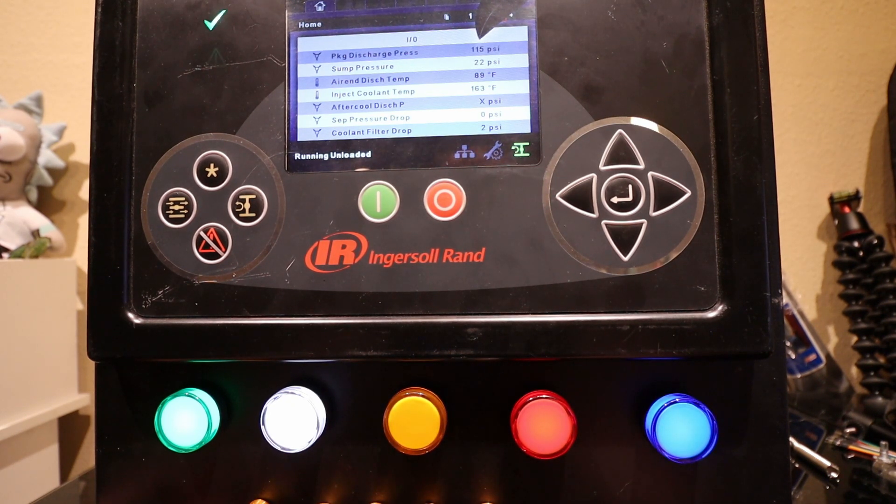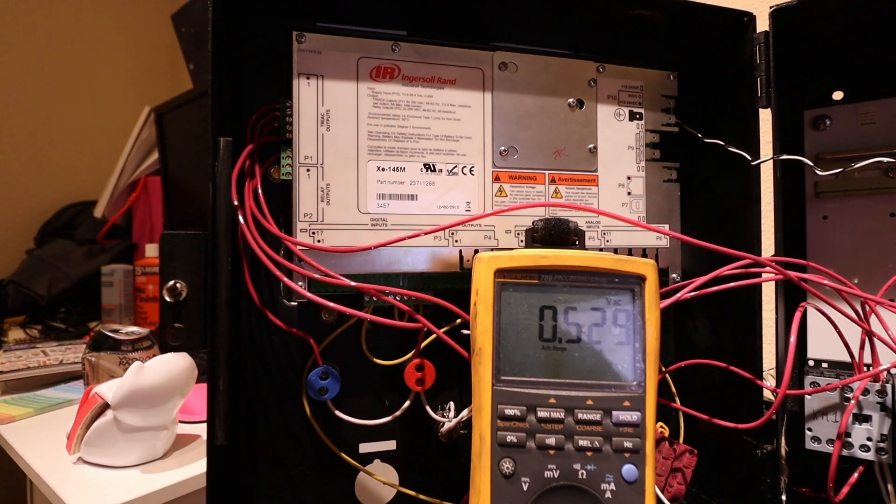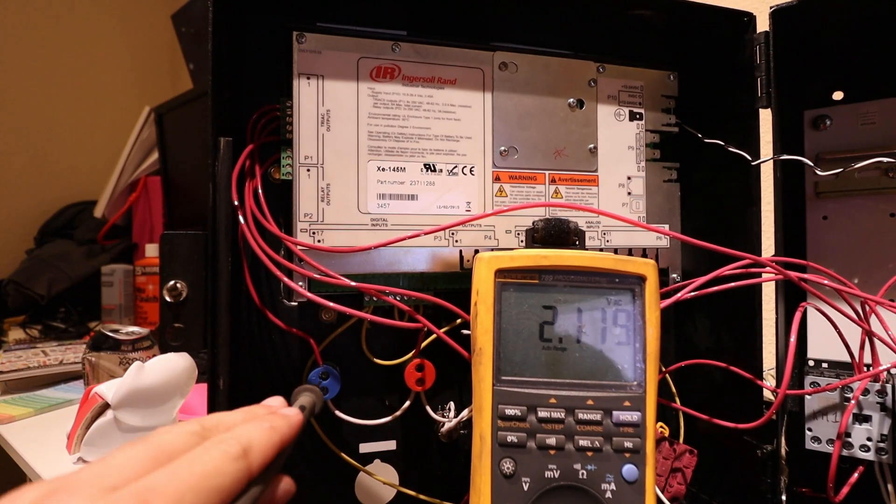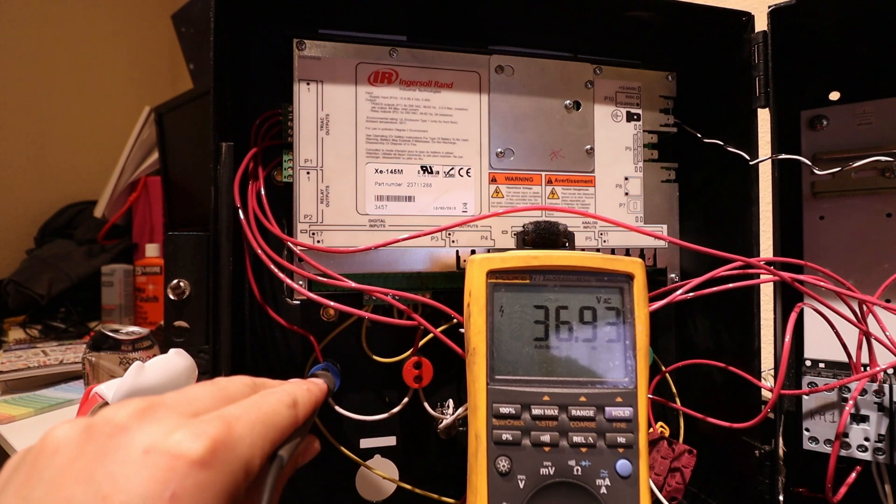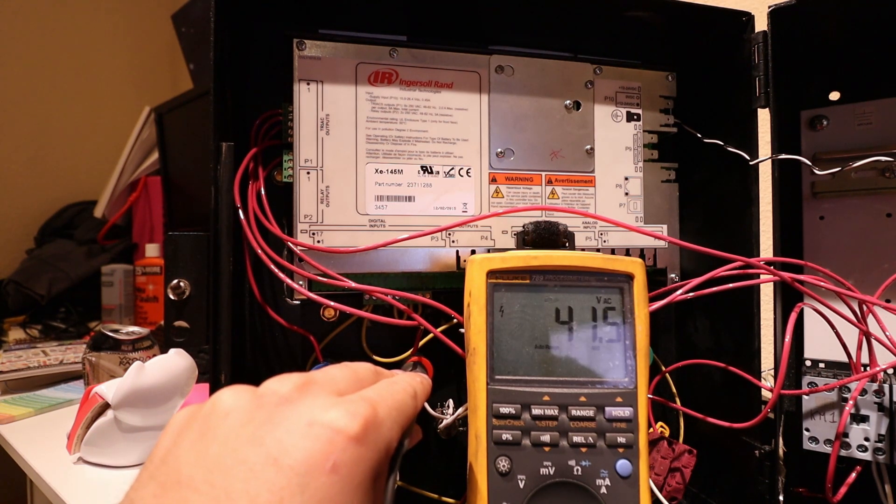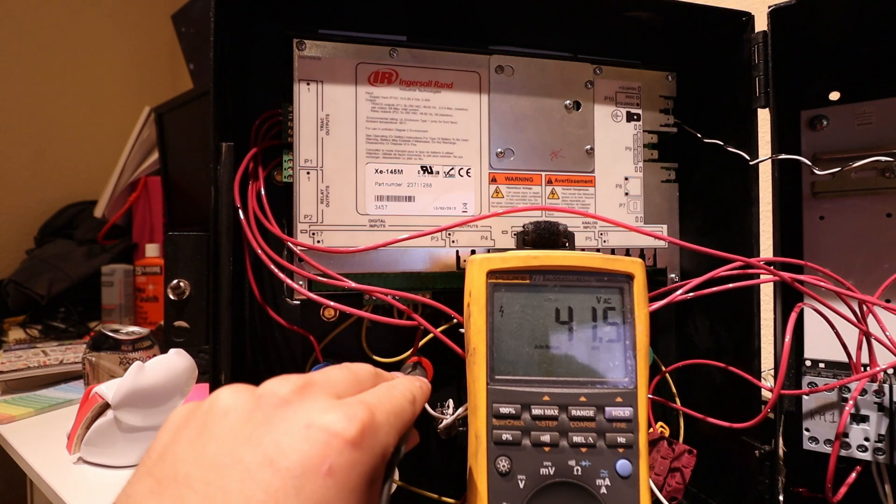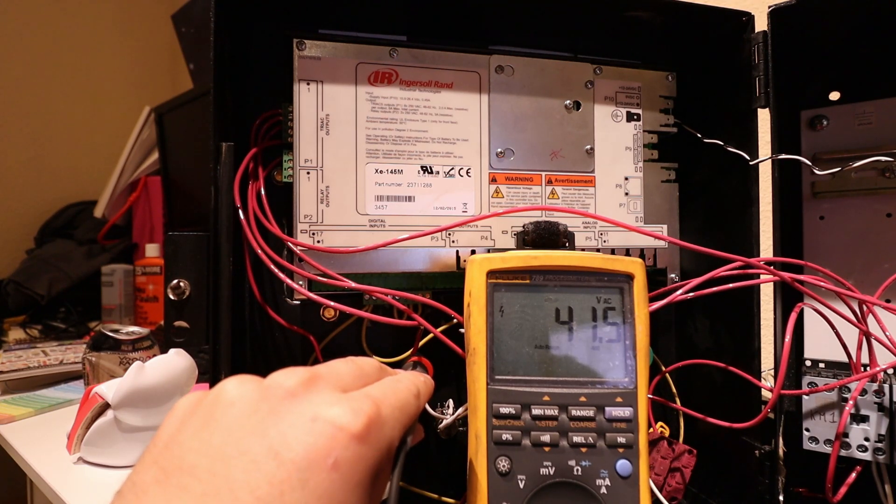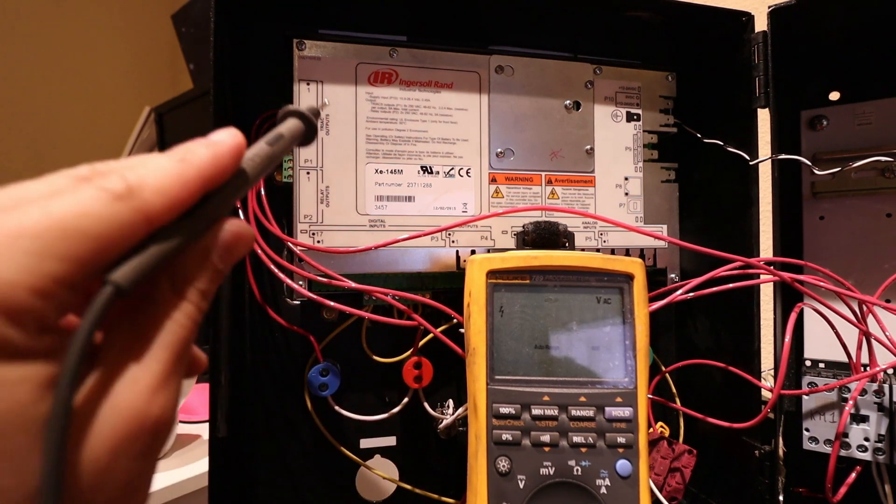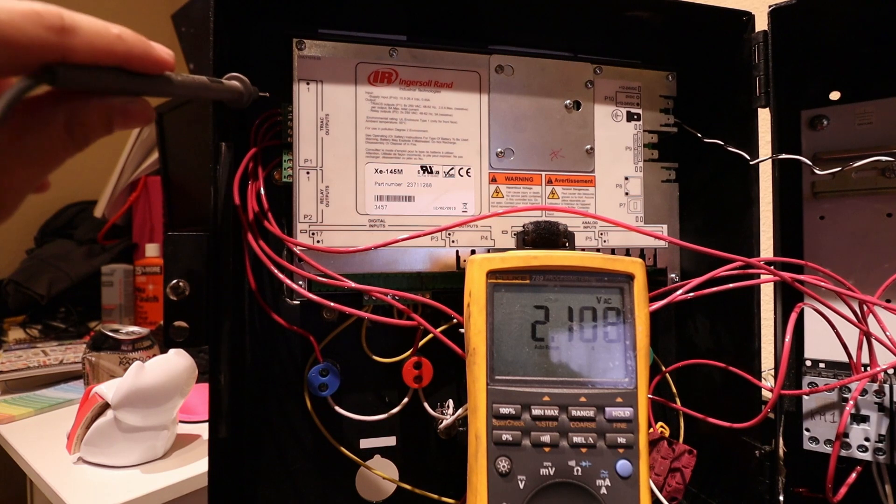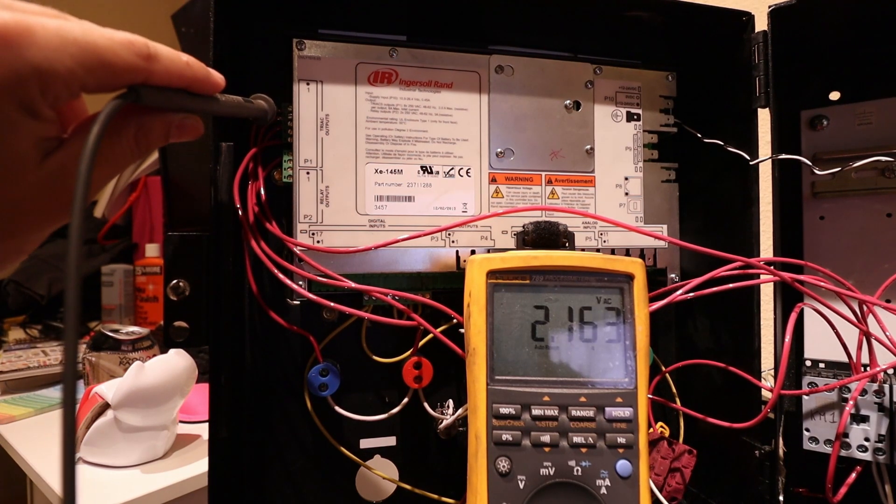If you see here, these blue and red colored lights that are a little bit on, they're getting 36 volts AC and 41 volts AC from the top left controller, the triac outputs. It's getting partial voltage, normally from a triac it's called ghost voltage, but it's partial voltage, and that's why they're partially illuminated. Whenever they're normally getting turned on, they're getting the whole 120 volts and they will illuminate entirely and become very bright.